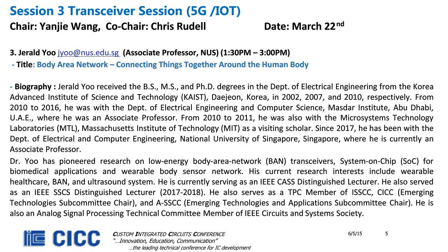So actually, I have a couple of questions. Dr. Yoo, on slide 12, when you were discussing galvanic coupling, I had a little bit of a question about the ground loop that could be introduced, particularly at the transmitter. What actually prevents a ground loop from happening right at the transmitter interface, thus basically taking all the energy from the receiver?